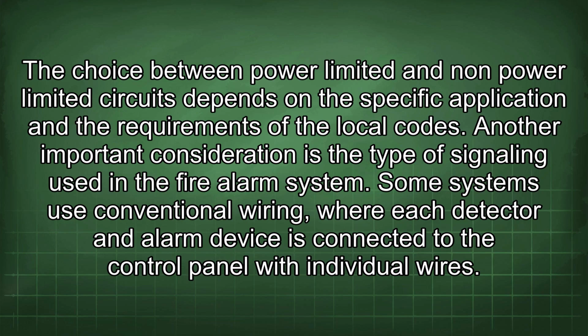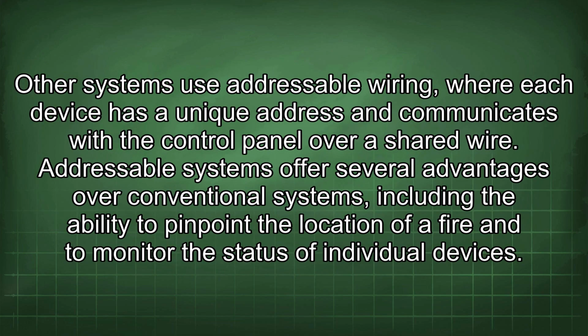Another important consideration is the type of signaling used in the fire alarm system. Some systems use conventional wiring, where each detector and alarm device is connected to the control panel with individual wires. Other systems use addressable wiring, where each device has a unique address and communicates with the control panel over a shared wire. Addressable systems offer several advantages over conventional systems, including the ability to pinpoint the location of a fire and to monitor the status of individual devices.